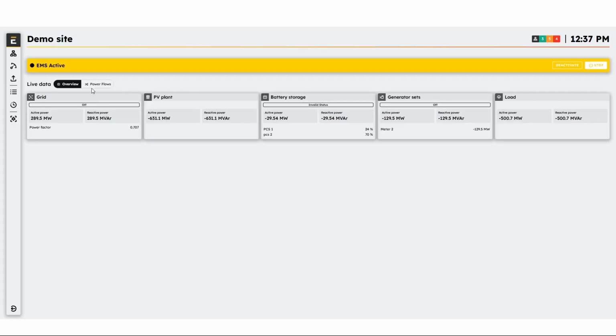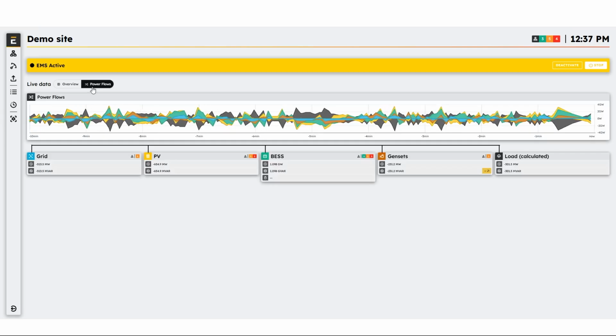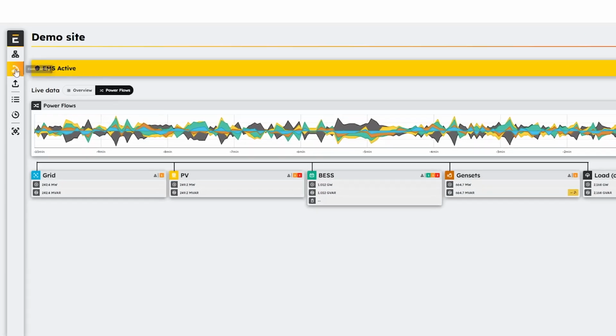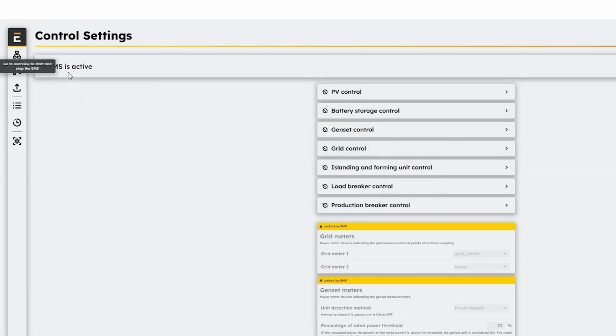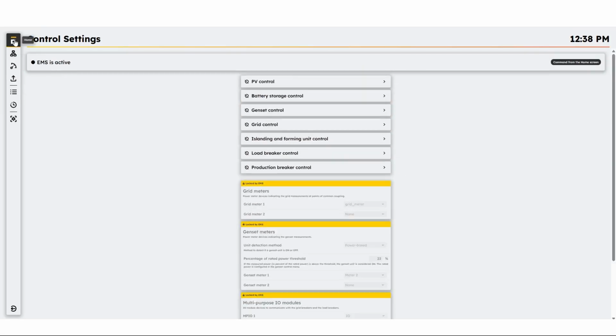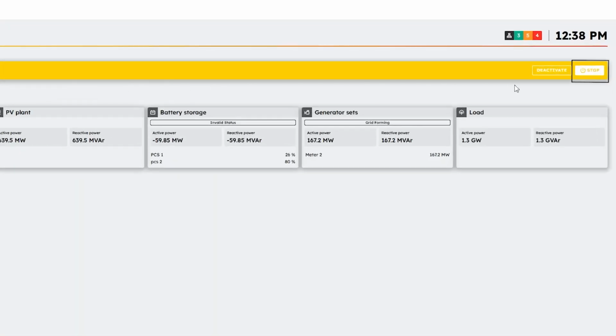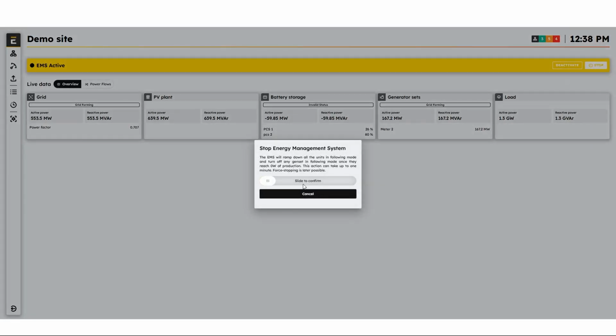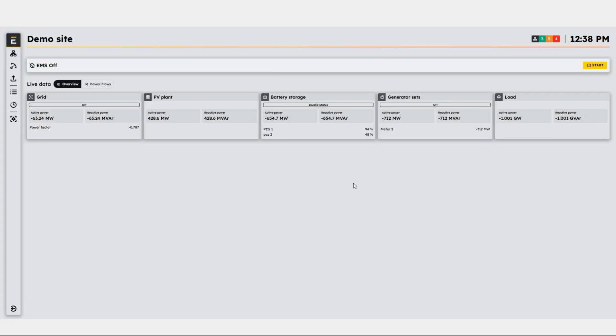Control Settings page is where you define how the EMS interacts with each power source and breaker on your site. Each section represents a specific control functionality that can be configured based on your system architecture. Please note that settings can only be changed when the EMS is stopped.